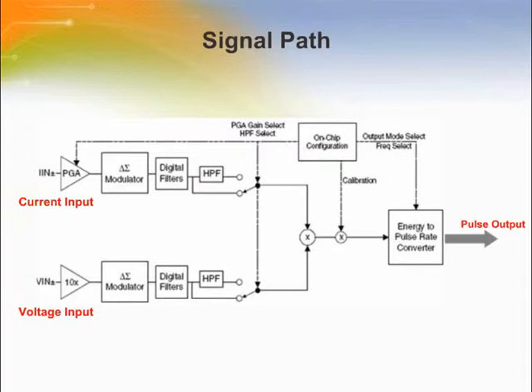This slide shows 2 data paths. The analog inputs are structured with 2 dedicated channels, voltage and current, then optimized to simplify interface into sensing elements. The voltage sensing element introduces a voltage waveform on the voltage channel input and is subject to a fixed 10 times gain amplifier. Simultaneously, the current sensing element introduces a voltage waveform on the current channel input and is subject to a programmable gain amplifier. Both amplified signals are sampled by delta sigma ADC converters for digitization.